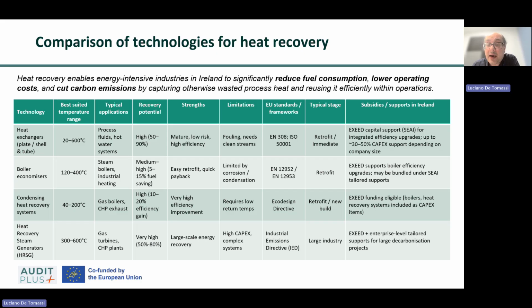Heat recovery steam generators are designed for high temperature waste heat streams generally between 300 degrees Celsius and 600 degrees Celsius or higher. They are most commonly used in combined cycle power plants, combined heat and power facilities, and large industrial processes. They can recover between 50 to 80% of available waste heat, converting it into useful steam for power generation or industrial processes. Their primary strength is their ability to capture very large quantities of high-grade waste heat. However, they involve substantial capital investment and are generally only economical at larger scales. They are a mature technology and can receive support through Irish industrial energy efficiency and decarbonization programs such as EXEED.